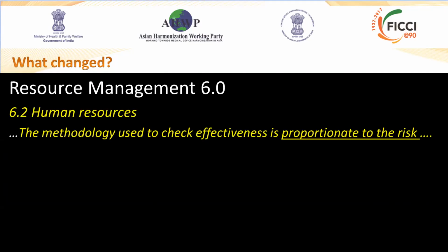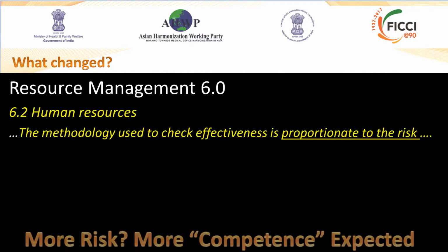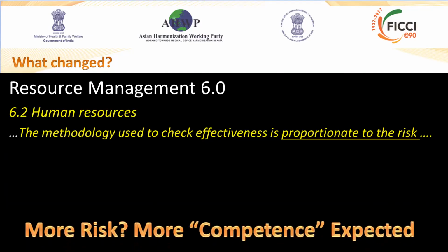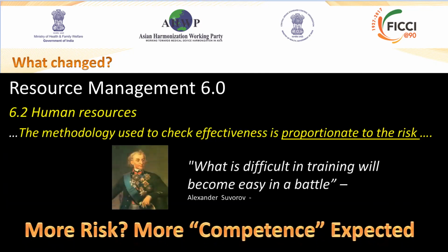Resource management is also to be done with regard to the risk level of the work that's being done. So if there's some work that's highly critical to the safety of a medical device, it's expected that the training will be a lot better, and the expectations for competency will be proportionate to that risk.